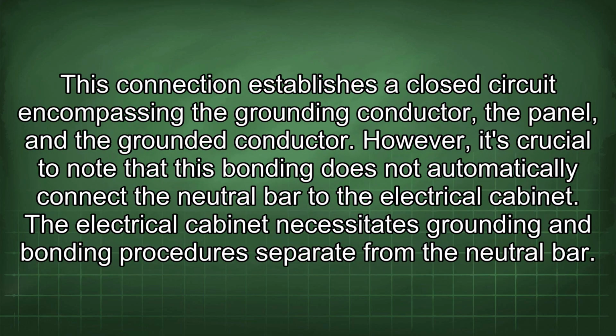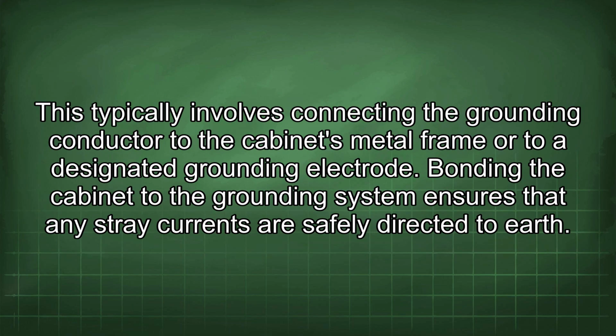This connection establishes a closed circuit encompassing the grounding conductor, the panel, and the grounded conductor. However, it's crucial to note that this bonding does not automatically connect the neutral bar to the electrical cabinet. The electrical cabinet necessitates grounding and bonding procedures separate from the neutral bar. This typically involves connecting the grounding conductor to the cabinet's metal frame or to a designated grounding electrode. Bonding the cabinet to the grounding system ensures that any stray currents are safely directed to earth.